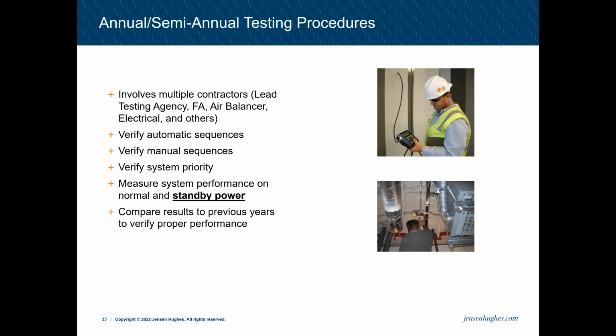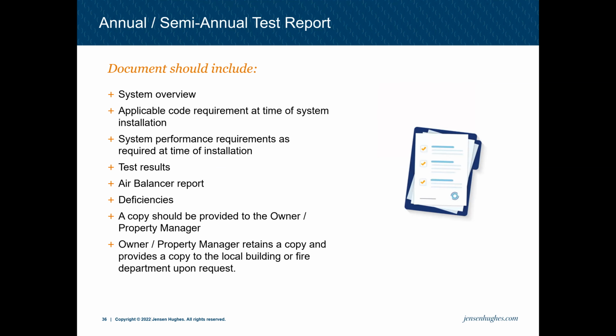Smoke control semi-annual testing does require an air balancer. It generally requires an electrician or electrical firm that can be there to do the emergency power test. And then, based on what the systems are, such as elevator pressurization, you might need an elevator tech and other technicians. These semi-annual tests should show the automatic sequence, manual sequences, system priority, and standby power. Following each test, a report should be provided, because the building owner must be able to provide these reports to the fire department as requested. Generally, the fire department will require these reports if a major renovation or a fire alarm project is being provided.